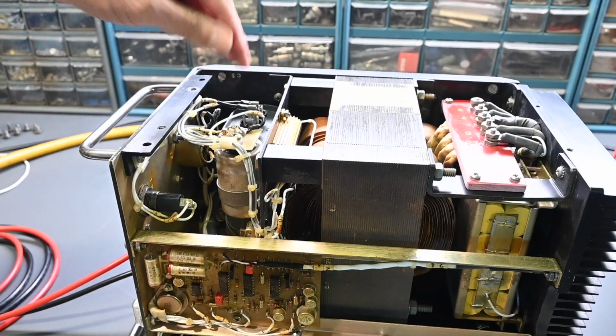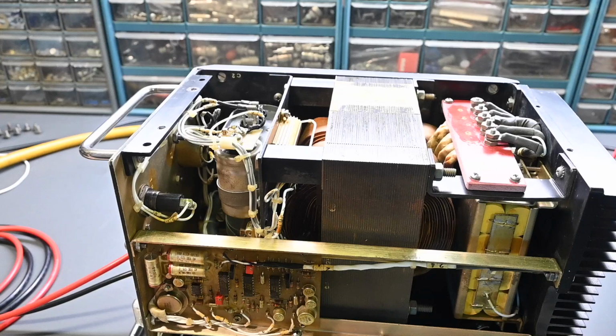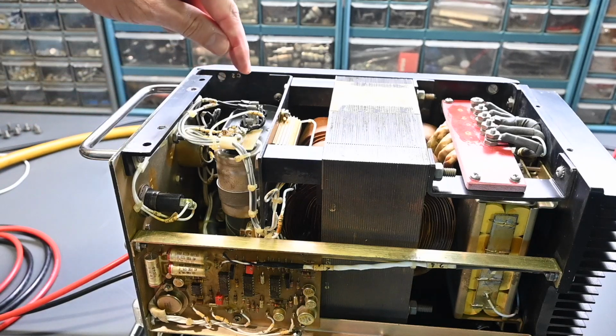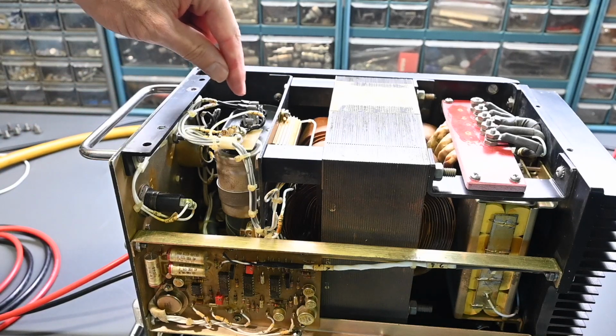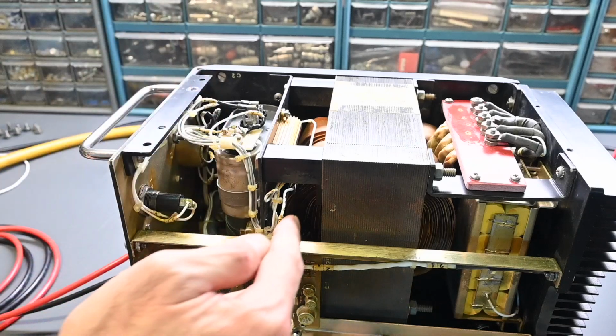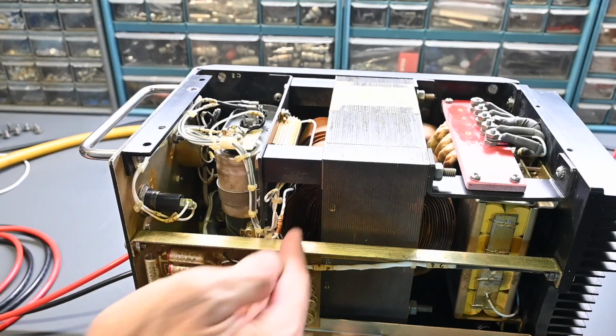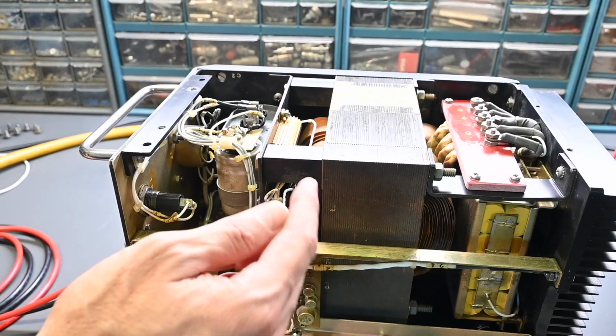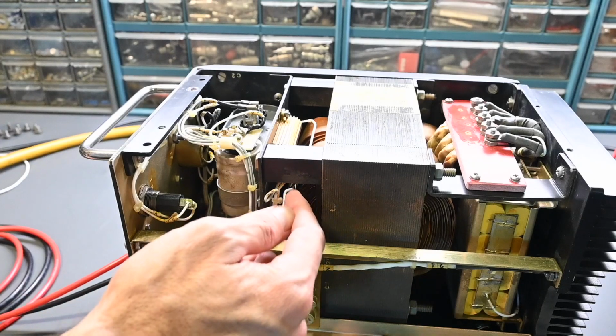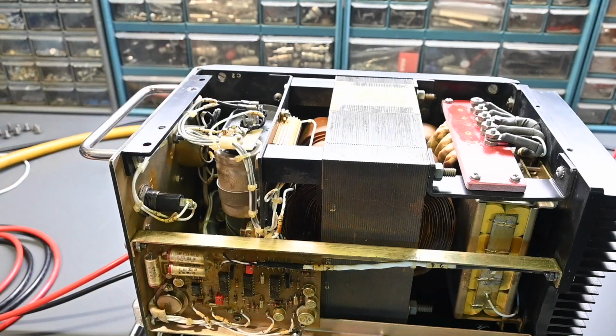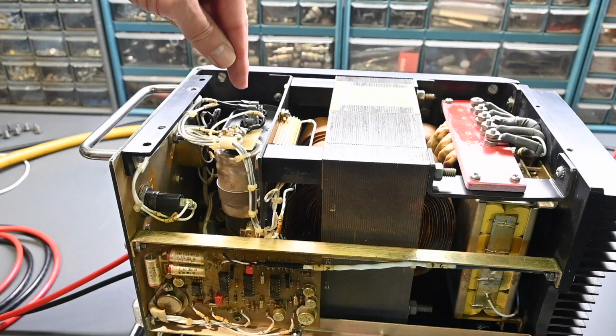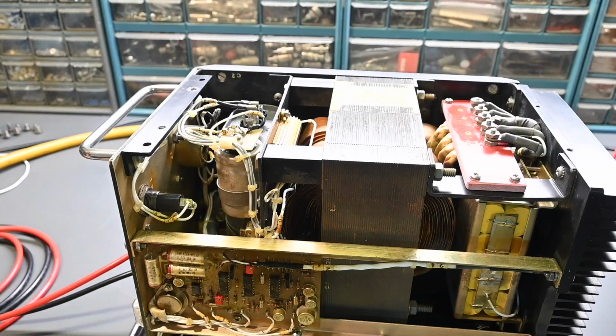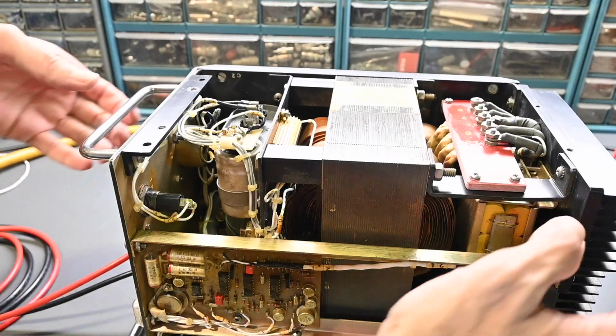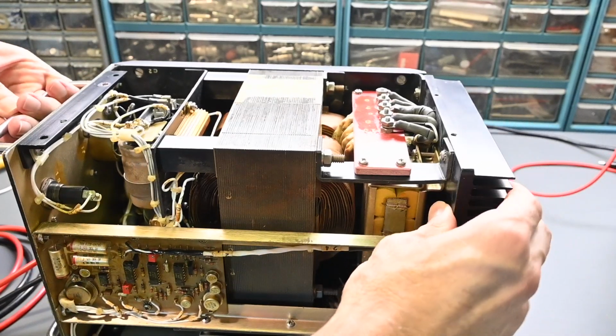That capacitor has almost 600 volts on it, and what I discovered is that one of the wires on this capacitor is ground, and the other wire comes right up here and goes right to the 600 volt tap on the transformer. So basically that tap only has one wire on it, coming from the tap over to that capacitor. They're essentially just putting this capacitor from the transformer's 600 volt tap to ground. I'm not sure exactly why they're doing that, or why such a high voltage.